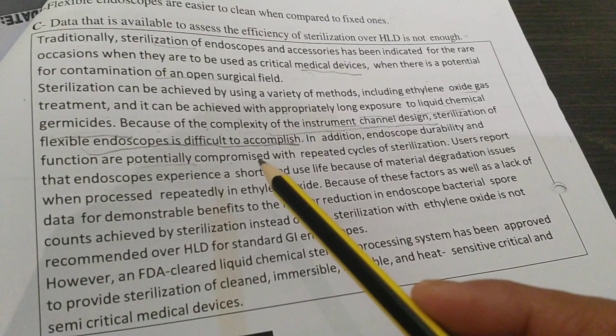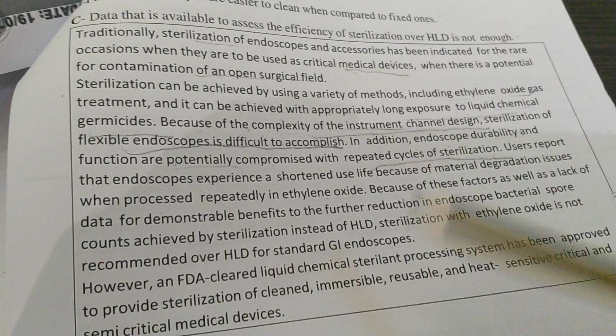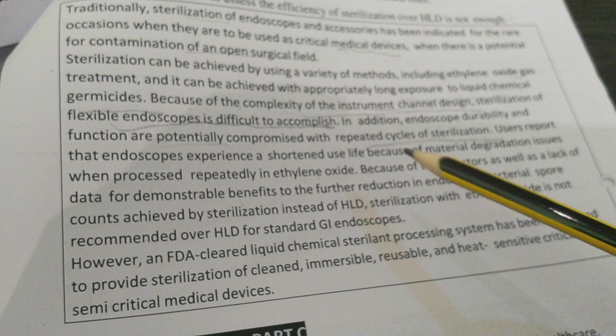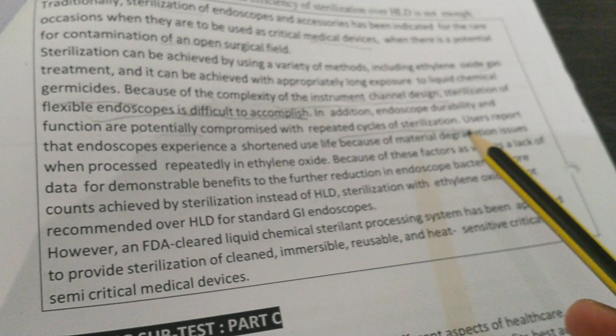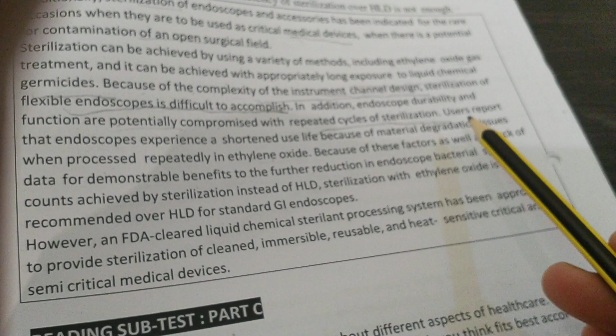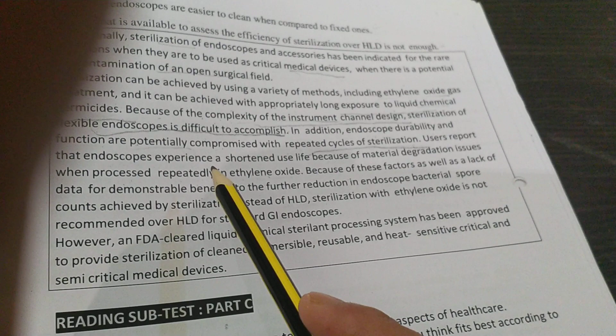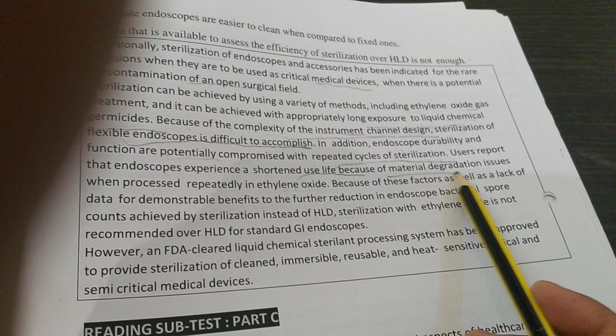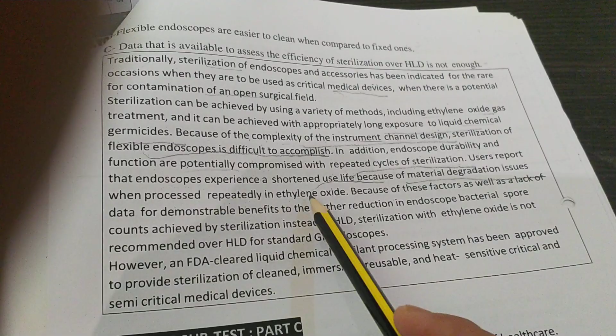In addition, endoscope durability and function are potentially compromised with repeated cycles of sterilization. As you know, if we clean some item repeatedly, it can get damaged in the future, especially if it's a rubber or plastic item, so it can affect the durability. Users report that endoscopes experience a shortened use life because of material degradation issues when processed repeatedly in ethylene oxide. So everybody is complaining that the life is shortened.